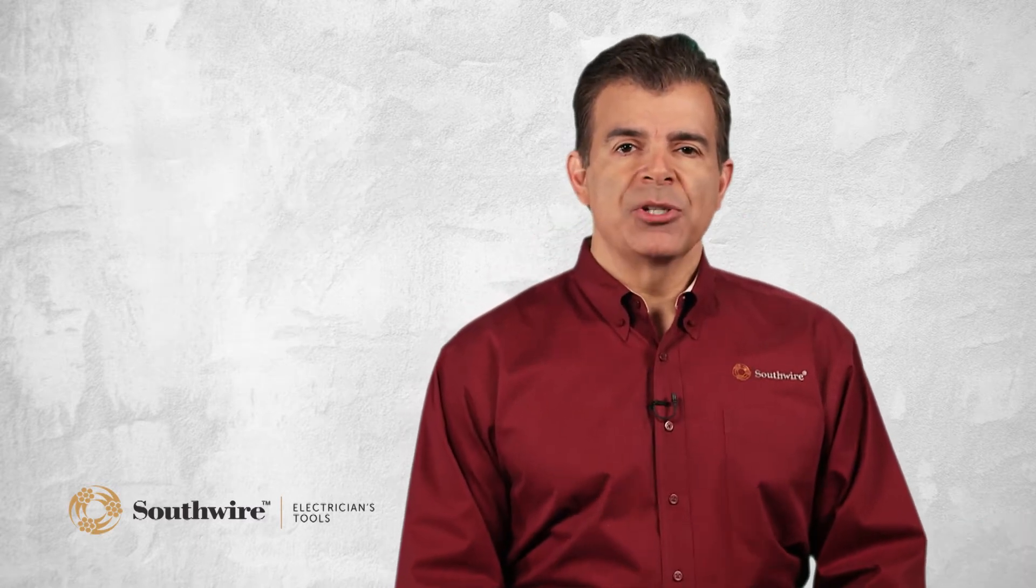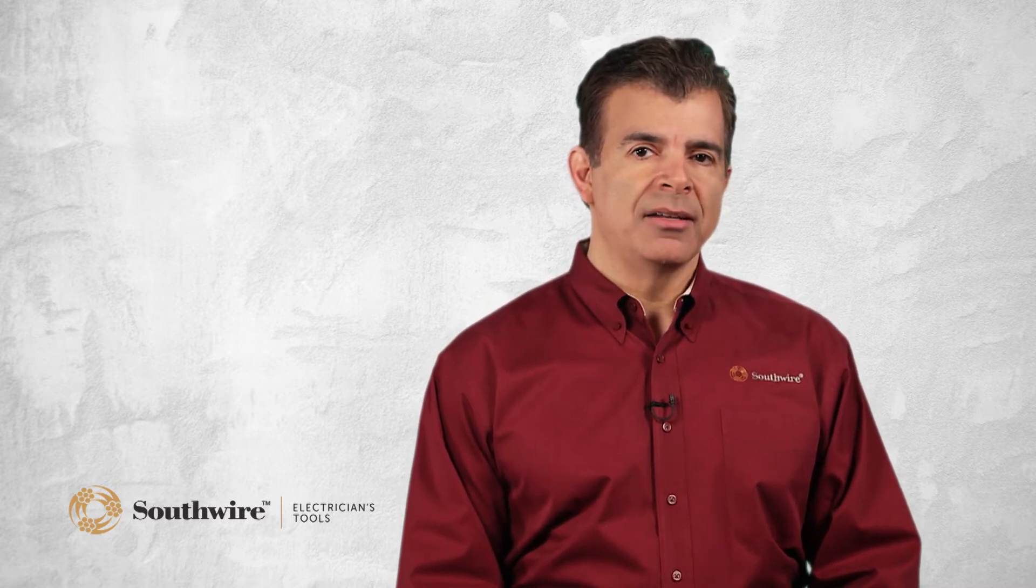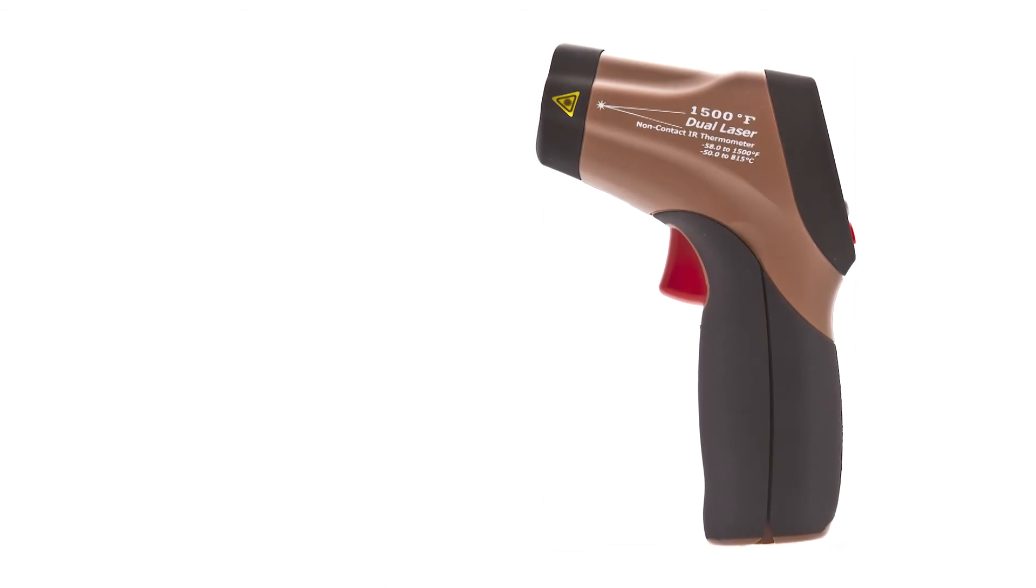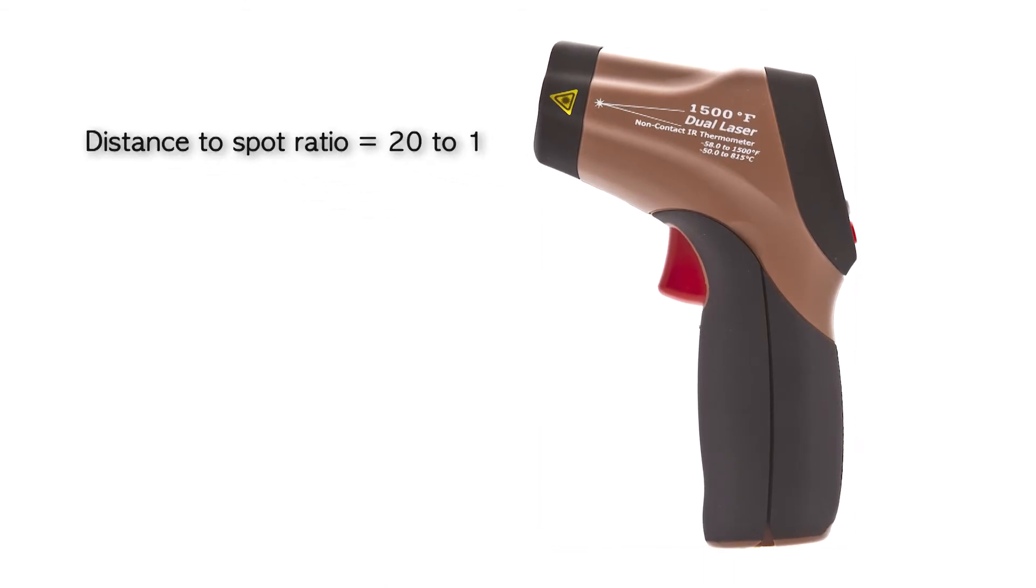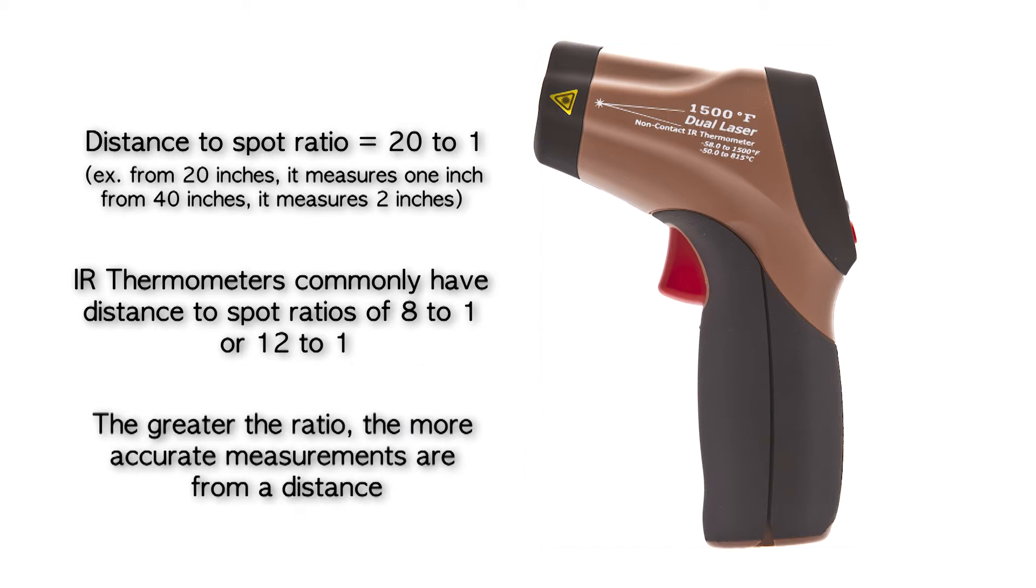Distance to spot ratio is a measure of resolution. It determines how far away a measurement can be made. For example, the top of the line Southwire 31040S has a distance to spot ratio of 20 to 1. So from 20 inches, it measures 1 inch. From 40 inches, 2 inches, and so on. IR thermometers commonly have distance to spot ratios of 8 to 1 or 12 to 1. The greater the ratio, the more accurate measurements are from a distance.